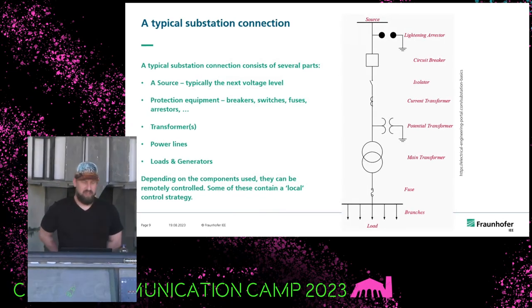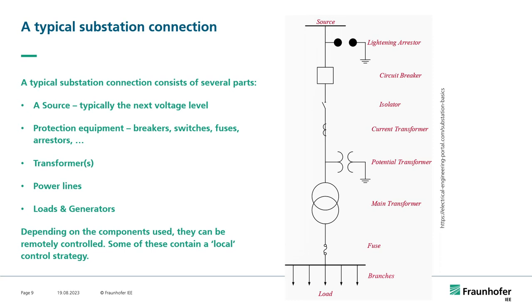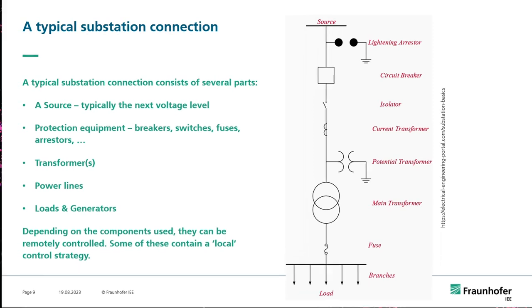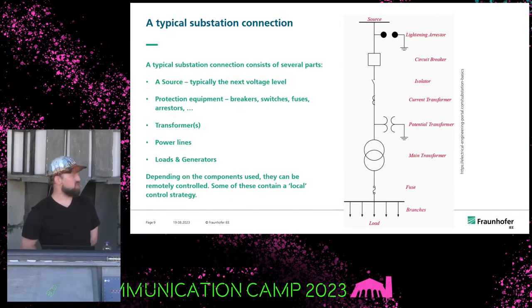But let's take a deeper look. A substation is the part you are normally connected to. How is such a substation built up or set up? You can see we have a source at the top, and then several protection equipment, for example this lightning arrestor, which is for overvoltage if there's lightning. Then we have a circuit breaker, the same thing you know from your normal household installation. We have the possibility to isolate, which means we can simply shut it off. And we have other transformers and stuff which will lead or transform down the power to go to you.